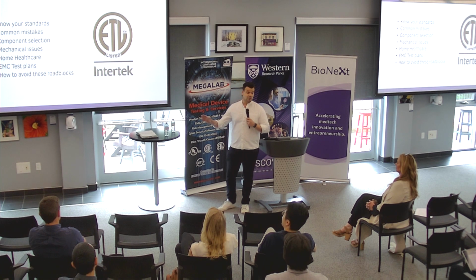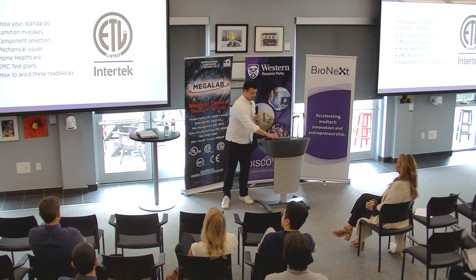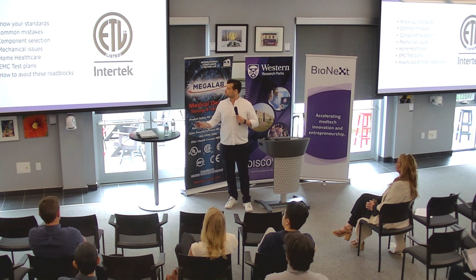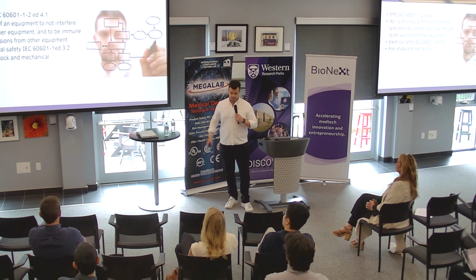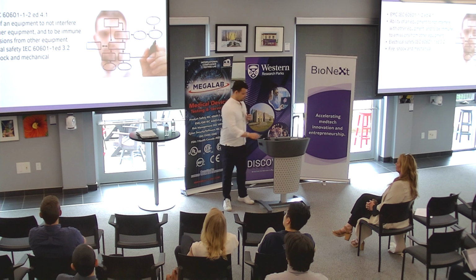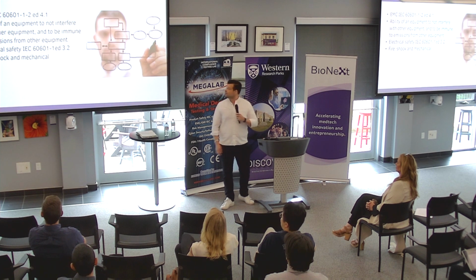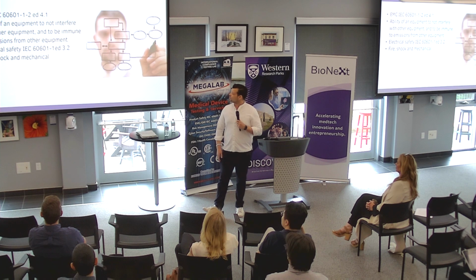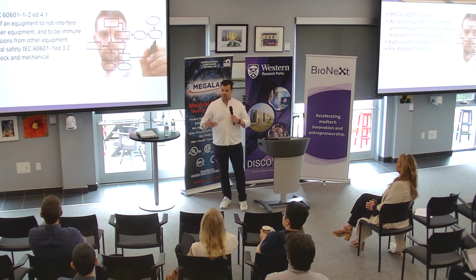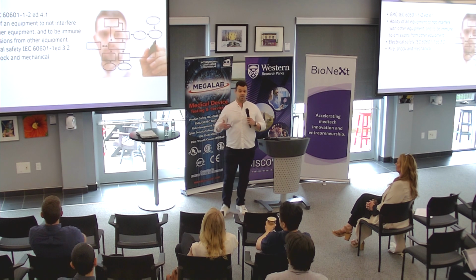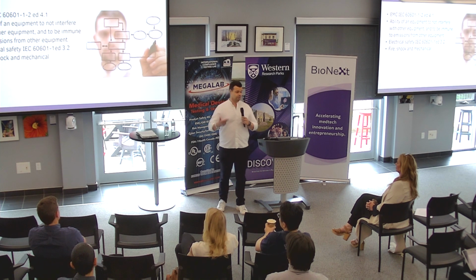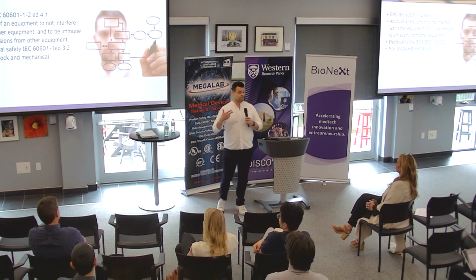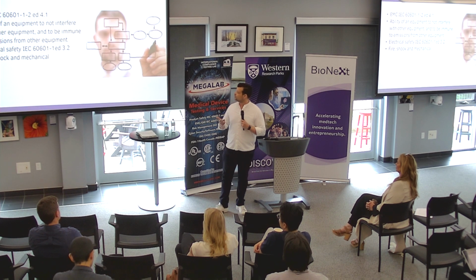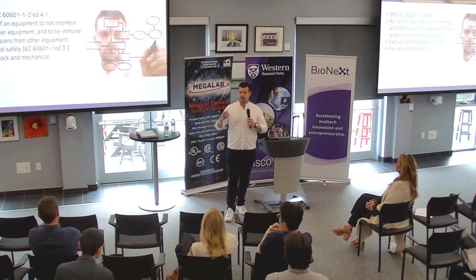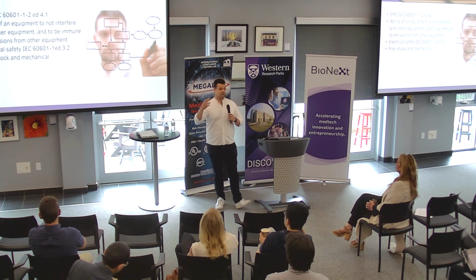There's many out there for medical devices. The main base one that you're going to come across a lot is IEC 60601-1. That one's -1-2. EMC testing. So that is electromagnetic compatibility. So if you want to sell your device and you want to get through your FDA and Health Canada, you're going to have to show them some test reports that you comply with this. So you don't want to have too many emissions, EMI noise coming off your device.